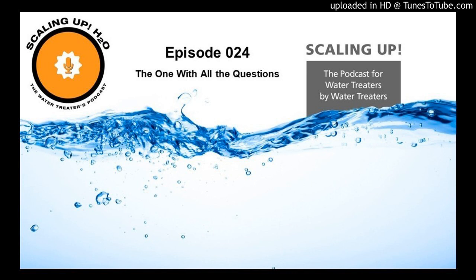Now that number is the saturation pH. What that means is it's the pH at which we are not dissolving calcium carbonate and we're not depositing calcium carbonate. Now you know. Well, let's go a little bit further.